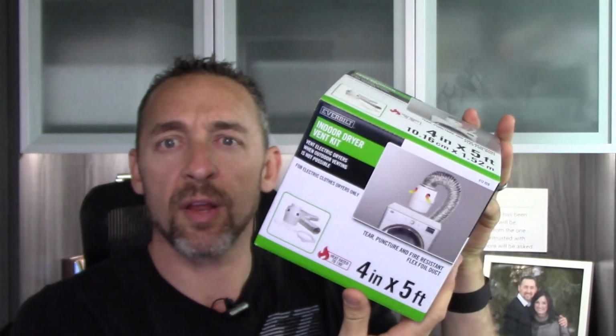Now, I know that there are these UL listed products you can buy at the store, like this thing here, where it's this recovery type of deal, where if you have an electric dryer, it says vent electric dryers to the interior. It's basically this water trap where it traps all the lint and you recoup all of the heat and moisture and it goes back into your home. These are bad news. I do not recommend these.